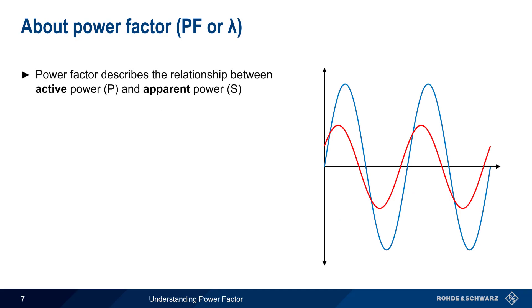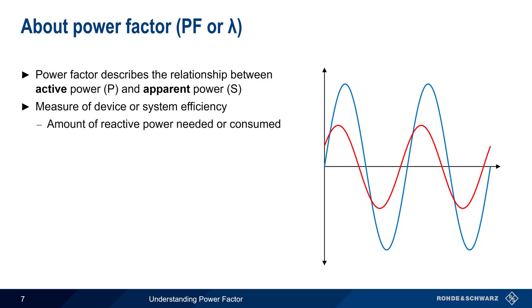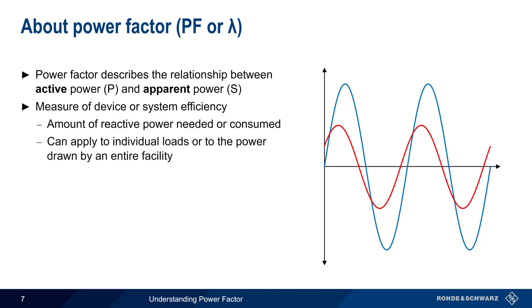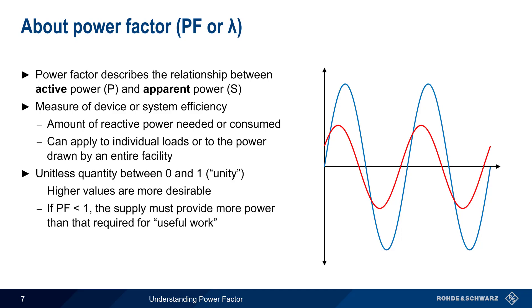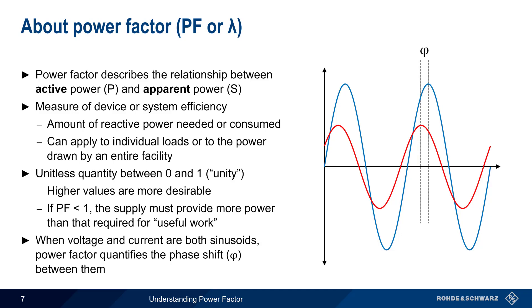Power factor, abbreviated PF or sometimes lambda, describes the relationship between active power — that is, power absorbed or used by the load — and apparent power, or the total power flowing in the circuit. Therefore, power factor is a measure of efficiency, since it's related to the amount of reactive power that's needed or consumed. Power factor can be measured for an individual device or load, or it can apply to a group of loads or an entire facility. Power factor is a unitless quantity between zero and one. Higher values of power factor are usually more desirable, and maximum efficiency occurs when power factor is one or unity, since this means there is zero reactive power. A power factor of less than one means that the supply has to provide more power than what's needed for useful work. Note that in the case where voltage and current are both sinusoids, power factor can be used to quantify the phase shift phi between the two waveforms.